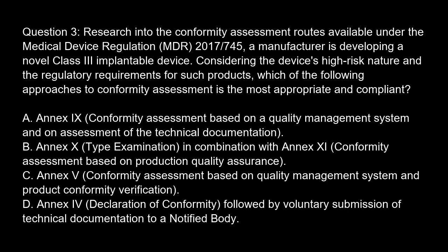Option A. Annex IX conformity assessment based on a quality management system and on assessment of the technical documentation. Option B. Annex X type examination in combination with Annex XI conformity assessment based on production quality assurance. Option C. Annex V conformity assessment based on quality management system and product conformity verification. Option D. Annex IV declaration of conformity, followed by voluntary submission of technical documentation to a notified body.